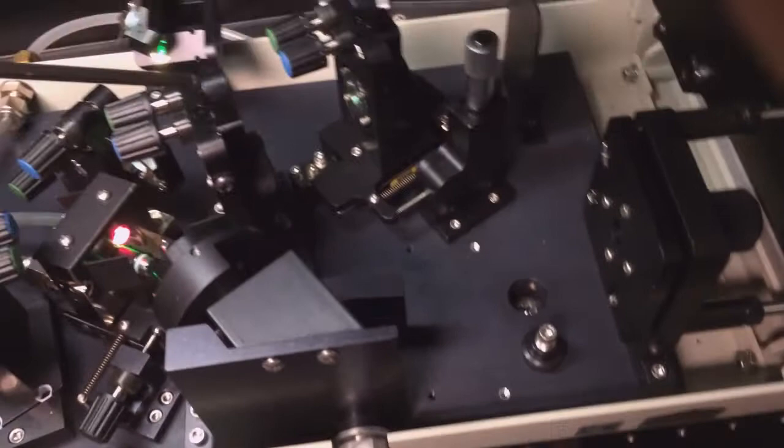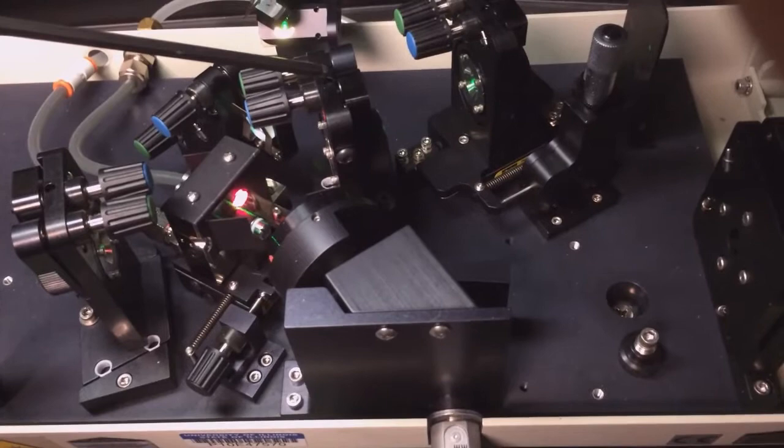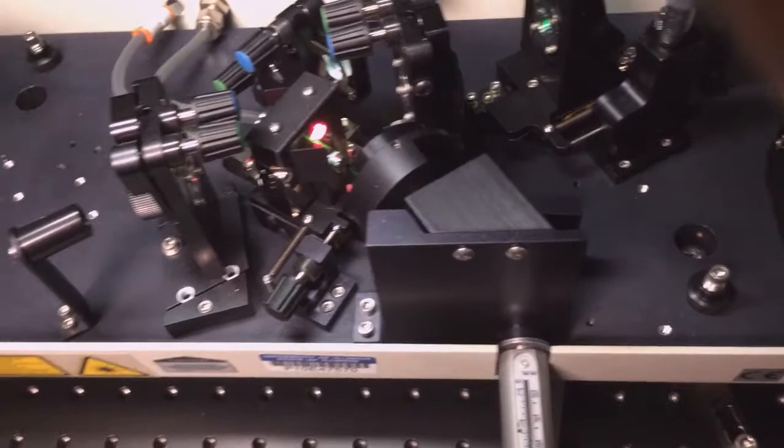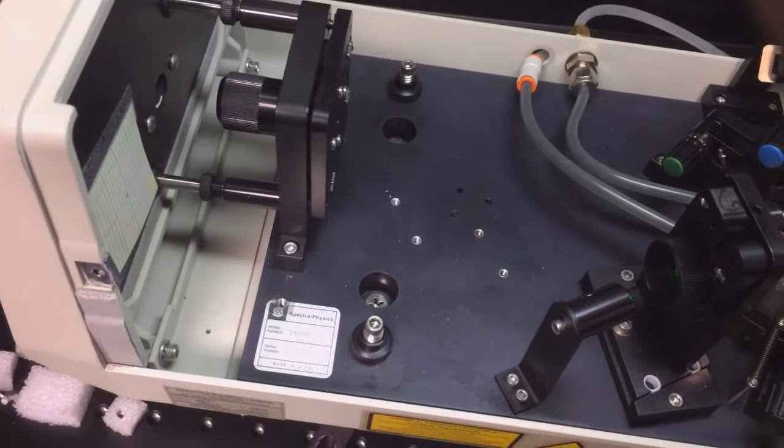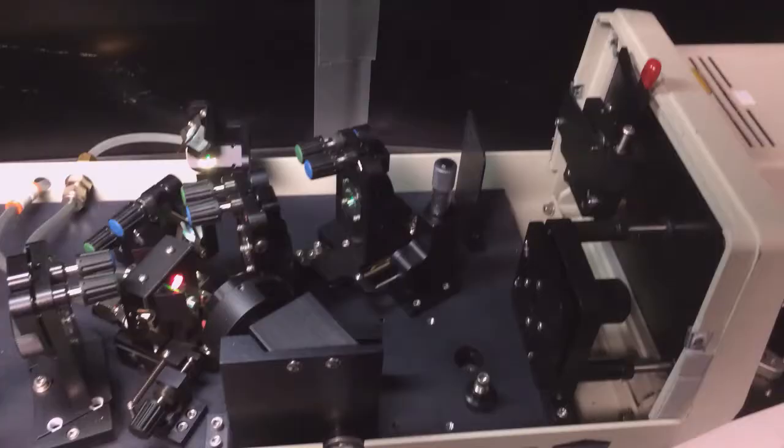This curved mirror is reflective for the near IR wavelengths and transmissive for 532. And then the beam goes to the output coupler over here which is also adjustable from the outside and can be used for daily optimization of the power, but it is suggested to start with the back reflector since the output coupler fixes the output mode which is perpendicular to the output coupler.